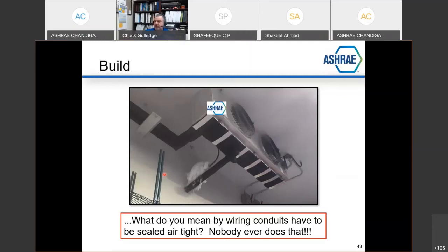Vapor pressure inside a freezer is so much lower than vapor pressure outside in a hot, humid climate. Moisture is going to push its way into this inside environment here. And just a simple unsealed electrical conduit that communicates outside of this box, there's enough moisture in there that you start making an ice dam. So they had to come in here with a blowtorch while this was operational, melt this ice off, get in there to seal that before it would stop doing it. Just an understanding of what vapor pressure differential means and the environment you're working with, getting back to those form issues in response to function.